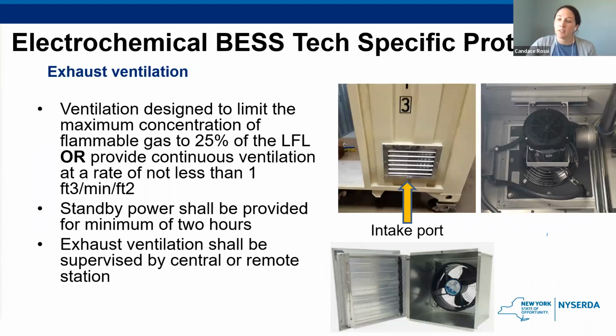So the first one we have here is the exhaust ventilation. So exhaust ventilation is required for rooms, areas, and walk-in energy storage units that contain certain electrochemistries. This is not required for lithium ion, but is for all other battery types. For example, lead acid batteries are capable of releasing hydrogen gas due to overcharging or other events. So this ventilation requirement is really focused on that. The applicant will need to install a ventilation fan for walk-in units with battery chemistries other than lithium ion.